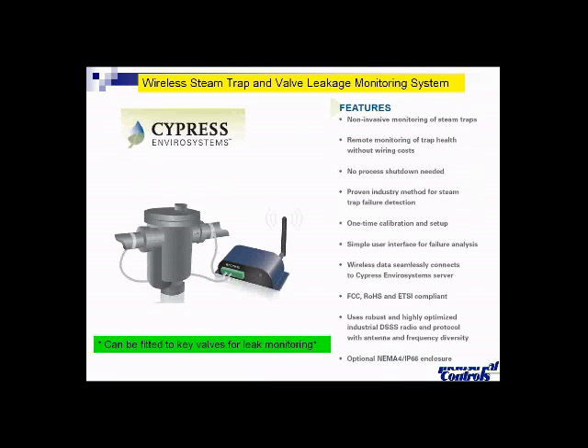What they're doing is they have a wireless transmitter that is connected to 2 temperature sensors that can be strapped on the upstream and downstream side of a key steam trap, or you can do this to any valve too, if you have a valve that's very important that you do not want to leak. And this wireless controller will do the math of the temperature differential. If it starts seeing the same temperature both upstream and downstream, and that valve is supposed to be closed, the logic would tell you that that valve is leaking.